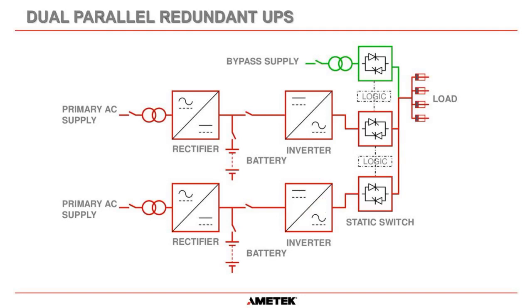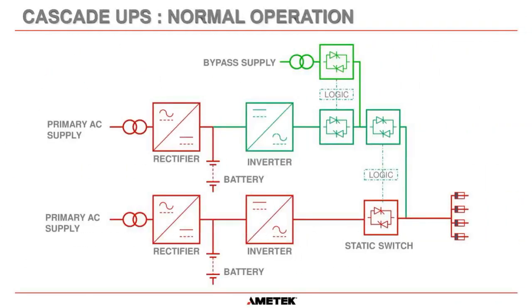Now, I suppose a lot of people, when we're talking about pros and cons of any system, really the biggest concern is a single point of failure. And really, we have two static switches here, and then we have a third static switch for our bypass supply. So a static switch isn't a single point of failure for us here. Really, the only single point of failure for us here is the wiring between the UPS and the distribution panel and the distribution panel itself. That is the only single point of failure on a parallel redundant system. So it's actually a very good system for your critical loads. So that was parallel redundant.